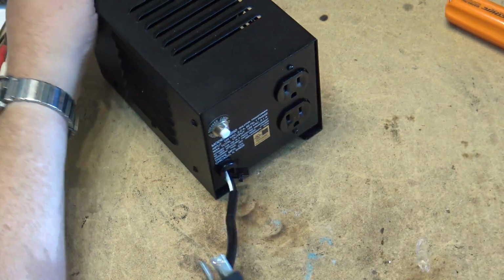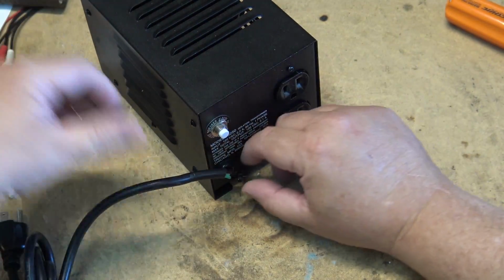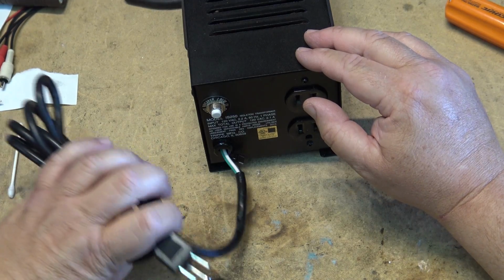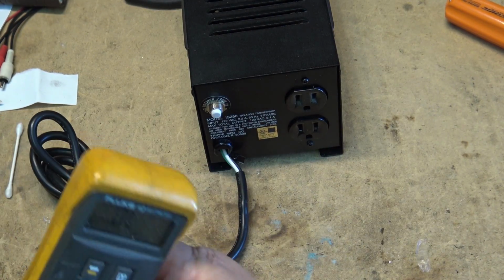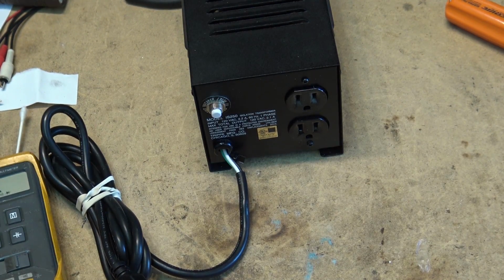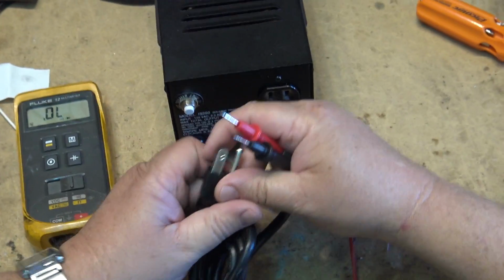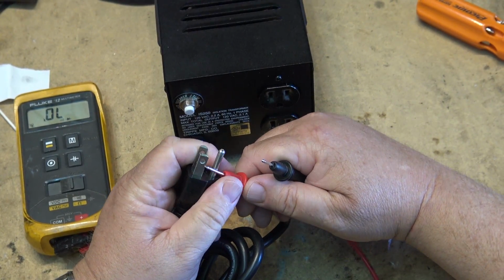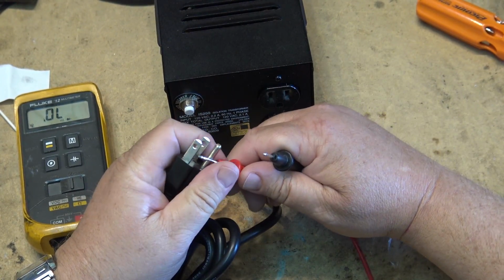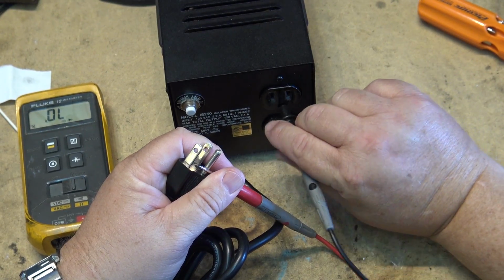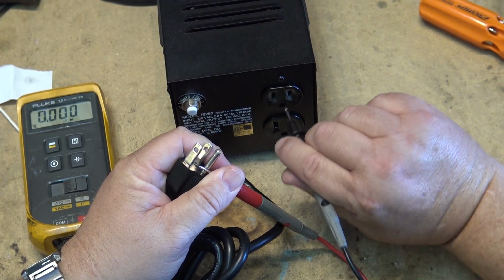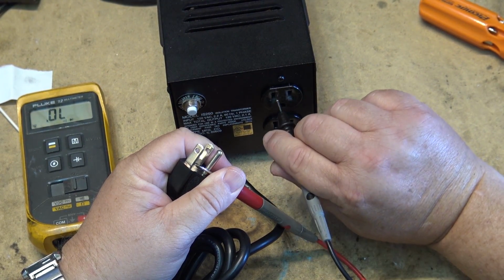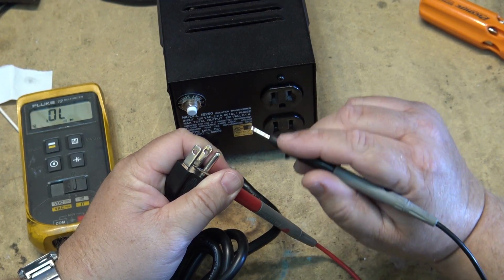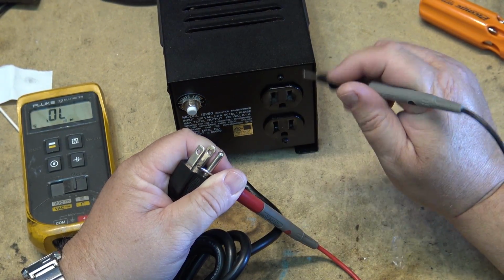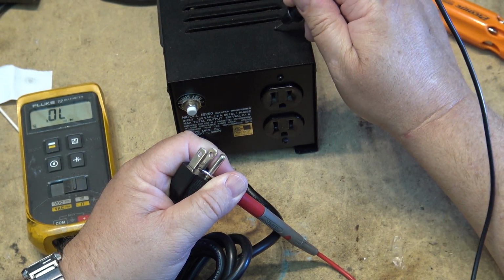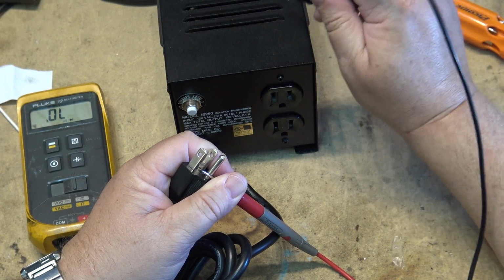The reason why this isolation transformer—oh, wonderful, the cord strain release is popping apart—the reason this isolation transformer is not suitable for service in its current form is because there is a reference to ground on the secondary. If I put my meter on the ground prong, you'll see that I have continuity. And that's because the ground terminal is connected to the secondary transformer, which is not acceptable.